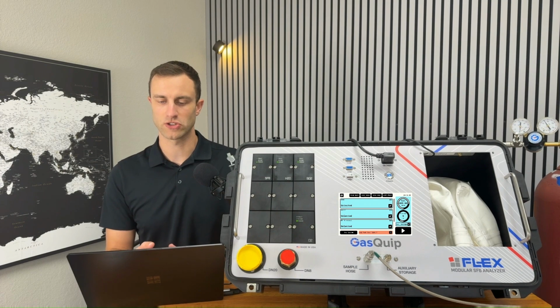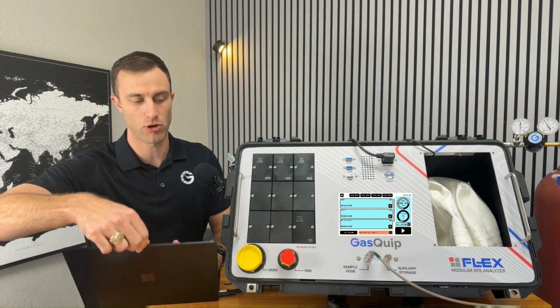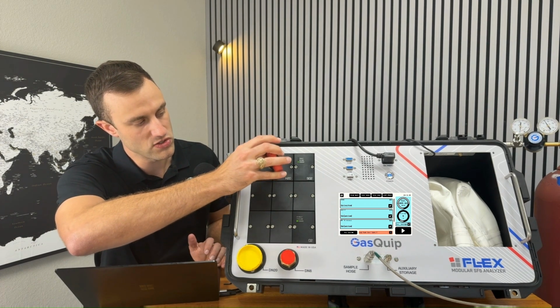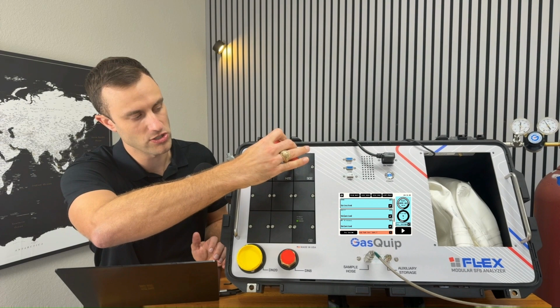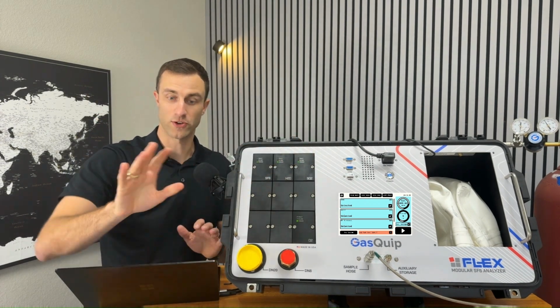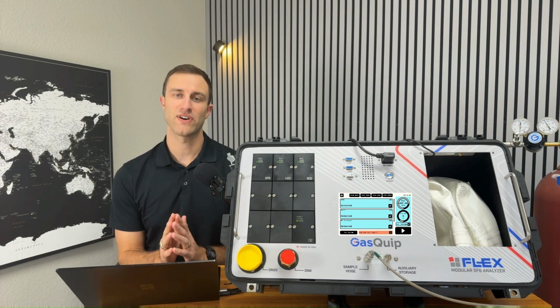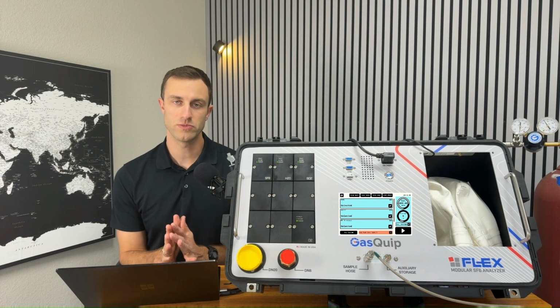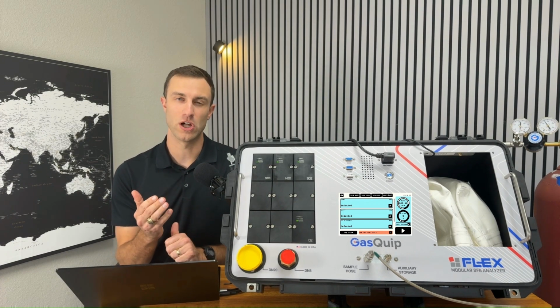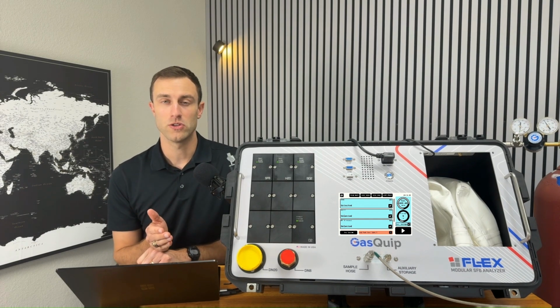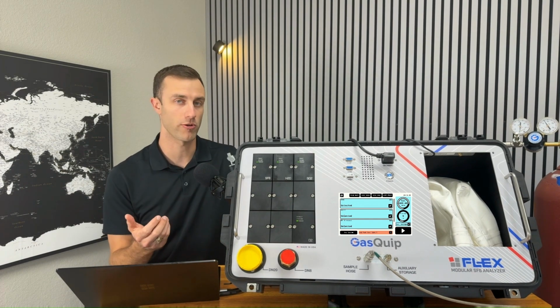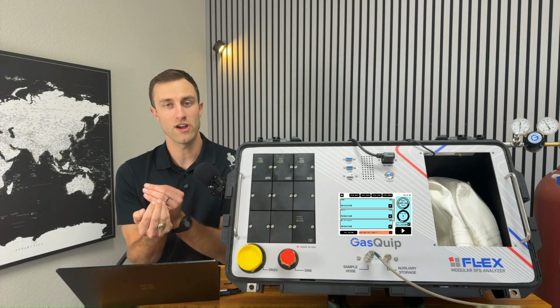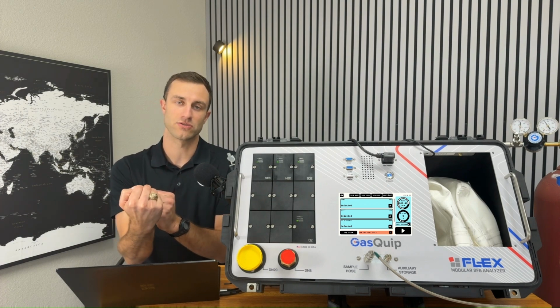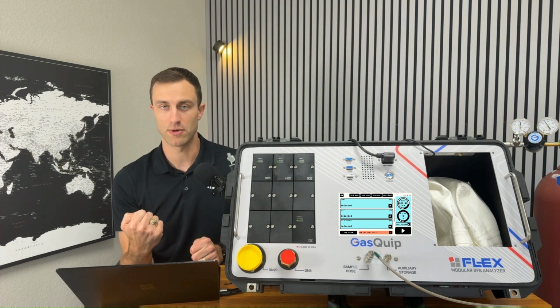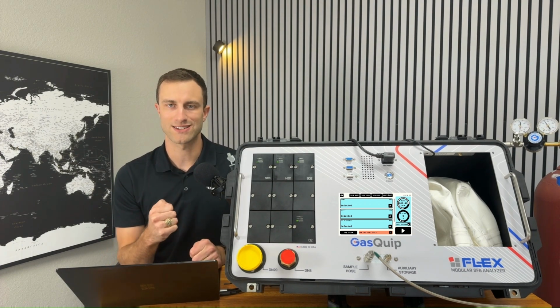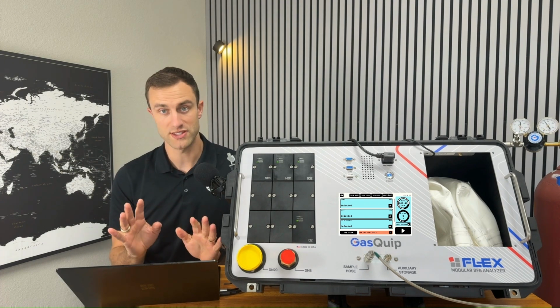The very first thing that I would do is make sure that your sensor modules are properly screwed in with your torque wrench. You're going to install that on either side of the screws and make sure that those are tightened down to spec. That's the first step. The second step would be to make sure you have at least 5 PSI showing on the home screen for the input pressure, and that you have good flow. Your hose could be kinked up. You could have a valve closed upstream on the breaker or something like that, where the pressure starts out with enough pressure in the hose, but as that gas travels into the analyzer, the pressure drops below the 5 PSI minimum pressure, and then it'll trip the Flex to stop the test because you don't have enough flow. That would be the second thing.